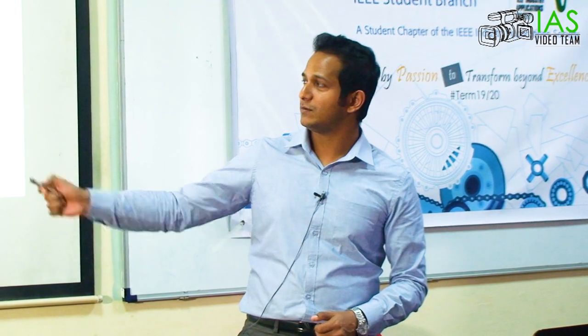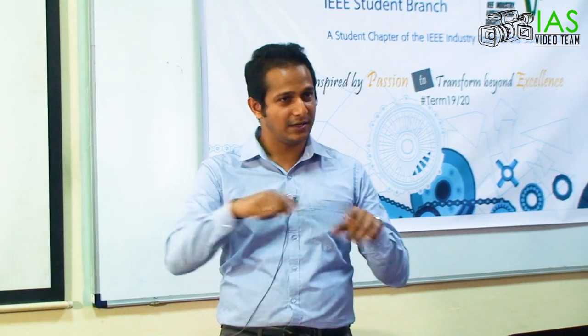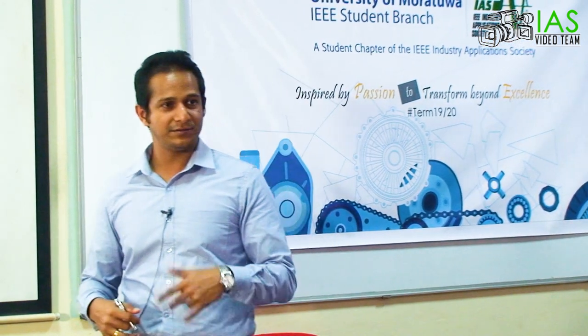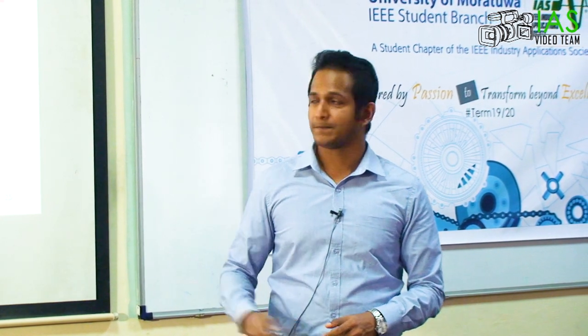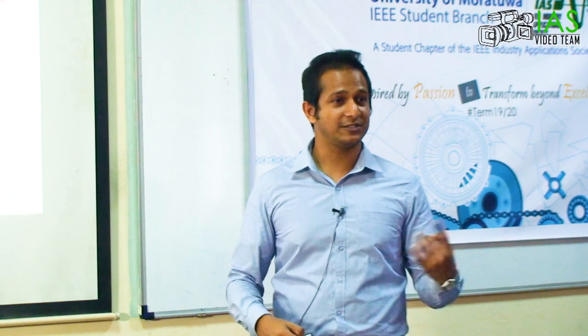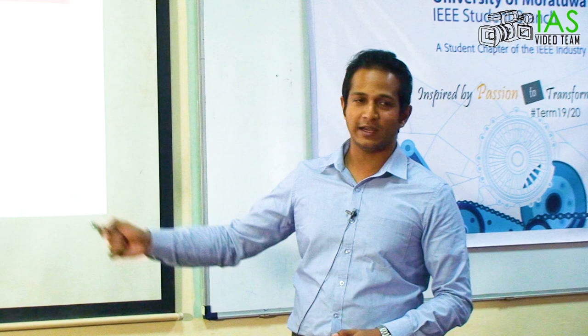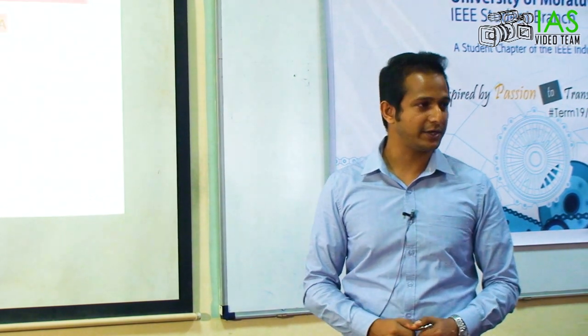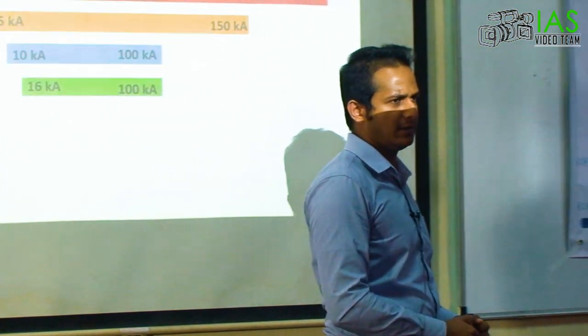When you go from class 4 to 1, the cost increases, because you have very close arrangement of copper arresters, copper tapes, and the grounding system. It all gets maybe double, triple, quadruple in terms of the material usage, and it reflects on the cost. But if your risk evaluation gives you class 1, then in order to protect the installation, obviously you have to go for class 1. If you install with class 4, nobody can guarantee that your installation is protected. And you would not be covered by the insurance maybe. Insurance matters.